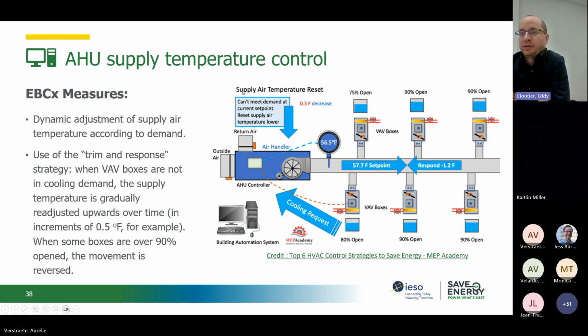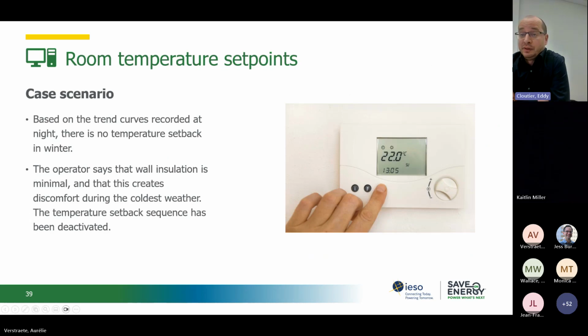Next slide, please. What you could do in that case is implement a trim and response strategy. Basically, you are looking at the different VAV boxes, and you are looking at whether a lot of them are over 90% open. If that is the case, you will reduce the supply temperature. If it's not the case, if there's very low cooling demand, you will gradually readjust the supply temperature by increments of 0.2 degrees Celsius or 0.5 degrees Fahrenheit, for example. And it will make it possible to save energy by reducing the need for terminal reheat. Next.